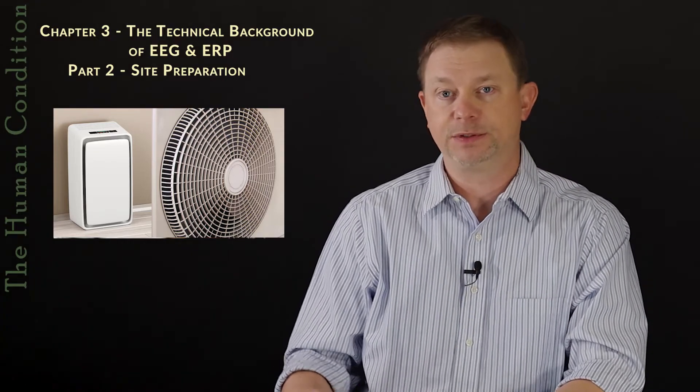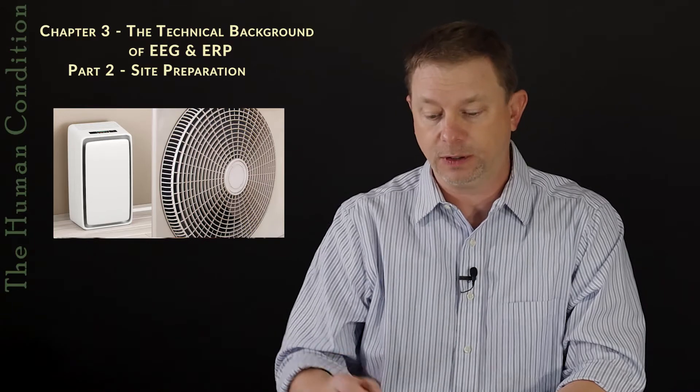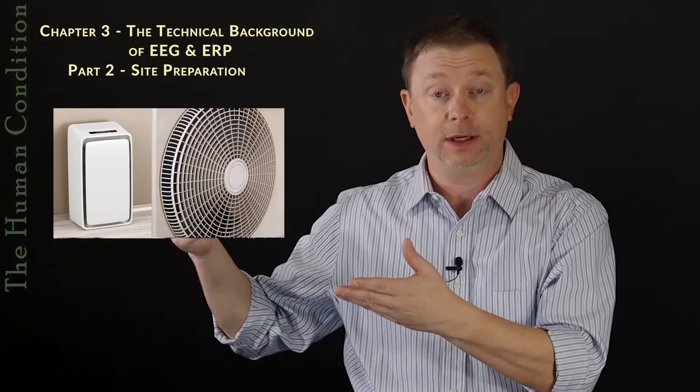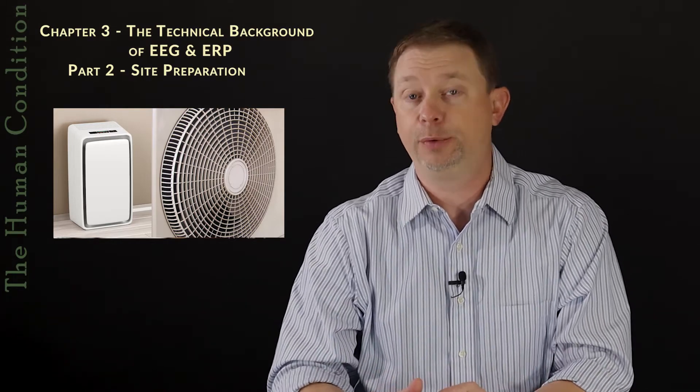So we have to make sure that we're not picking up a 60 cycle hum in the United States or a 50 cycle in Europe or somewhere else. We don't want to see electrical noise come across from the power source of a fan or an air circulator or an air purifier.